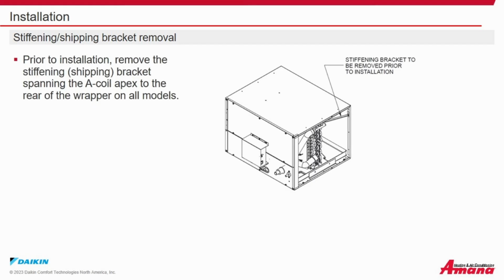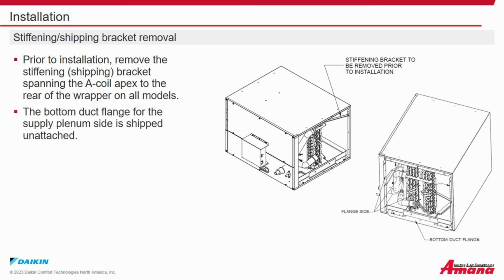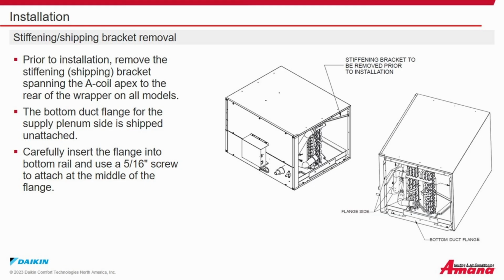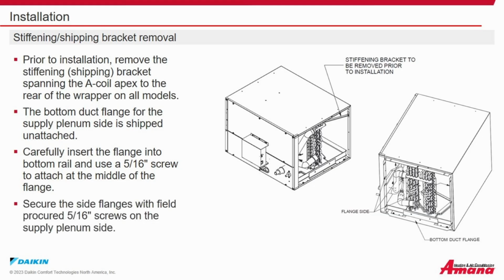Stiffening or shipping bracket removal. Prior to installation, remove the stiffening or shipping bracket spanning the A-coil apex to the rear of the wrapper or cabinet on all models. The bottom of the duct flange for the supply plenum side is shipped unattached. Carefully insert the flange into the bottom rail and use a 5/16 inch screw to attach at the middle of the flange. Screw the side flanges with field-supplied 5/16" screws on the supply plenum side.